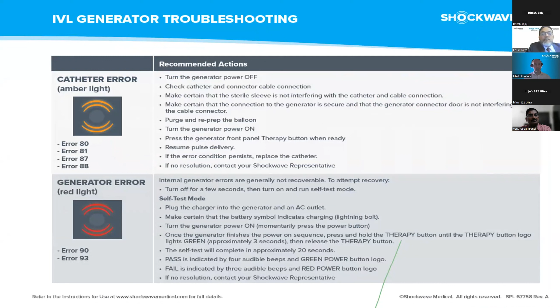So on to what we look at if we're in the lab. As physiologists, everybody will turn to us and say the catheter is broken or the generator is broken, and we will get up to 4 yellow amber lights as error codes: 80, 81, 87, and error 88. And we may from time to time see the error code on the red light, error 90 and 93. So I'll start with the red light first, the error messages 90, 93.